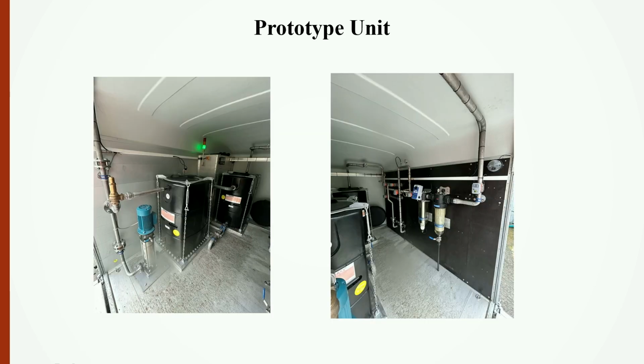It's inside a towable container because this is to be used at the point of commissioning. Well, before you commission, at the point of installation, before you commission it, you will test it to make sure it's actually worth commissioning. On the left side of this container there, you can see the 2 degassing tanks, a motive pump. We have a pressure release valve there, which means if someone's misprogrammed the system and we're in danger of bursting the pipe, that's going to blow first.